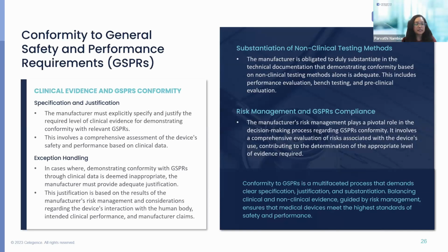So while demonstrating compliance or conformity to these GSPRs, what we need to see is that the device performs as intended, is safe for its use, and that the benefits associated with the use of the device are higher than the risks associated with it. So once all of this data is presented, and appropriate cross-referencing needs to be done in the document so that the notified body reviewer can go back to the relevant sections and see that the data has been presented elaborately in the section and has been summarized accordingly in the conformity to GSPR section.